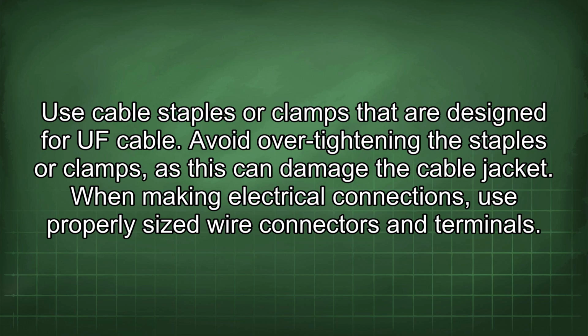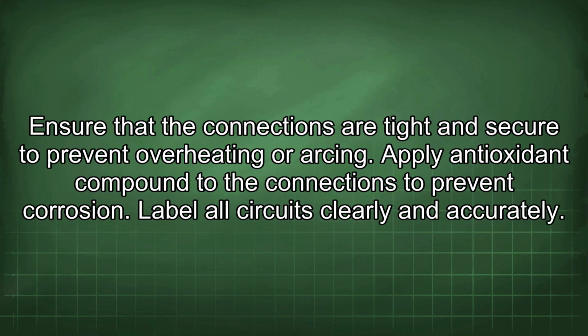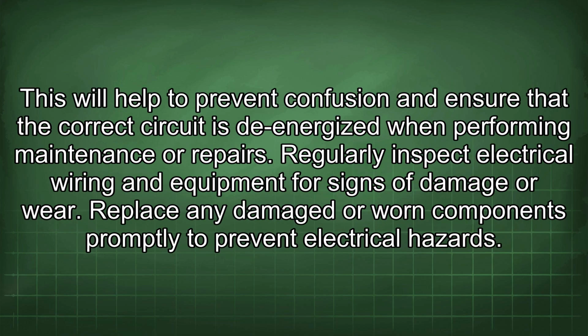Avoid over-tightening the staples or clamps, as this can damage the cable jacket. When making electrical connections, use properly sized wire connectors and terminals. Ensure that the connections are tight and secure to prevent overheating or arcing. Apply antioxidant compound to the connections to prevent corrosion. Label all circuits clearly and accurately. This will help to prevent confusion and ensure that the correct circuit is de-energized when performing maintenance or repairs.